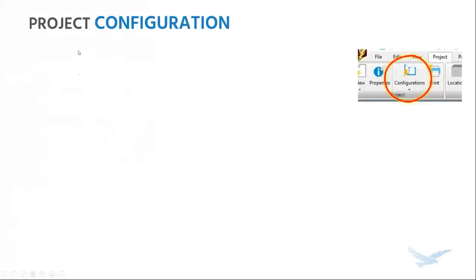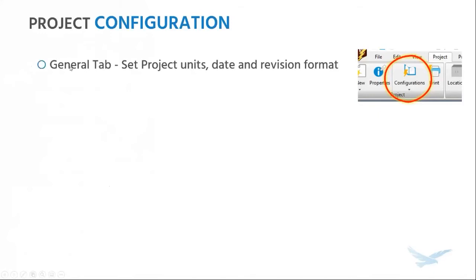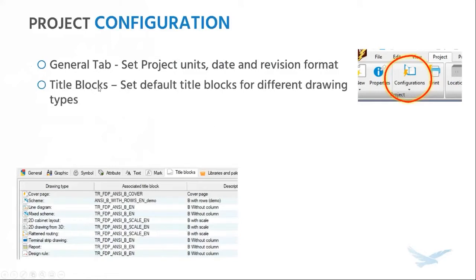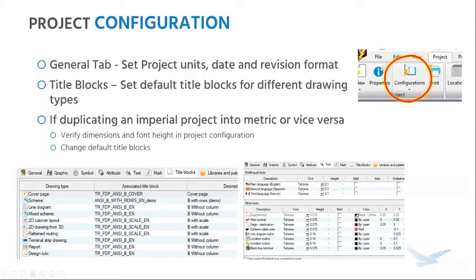A bulk of the work is going to happen in project configuration, which has about six or seven tabs. In the general tab, you're going to be setting up the project units, format for dates and revisions, among other things. In the title block tab, you will be setting up the default title block for different types of drawings — so if you mostly use B-size paper, when you create new schematics it should start with a B-size title block. It is possible to change the title blocks on a one-off basis, but good to set up these defaults. If you plan on duplicating an imperial project into a metric project or vice versa, take a closer look at dimensions and font height in project configuration — a one millimeter font in metric translates into one inch font in imperial. Make sure to relink to an appropriate title block.